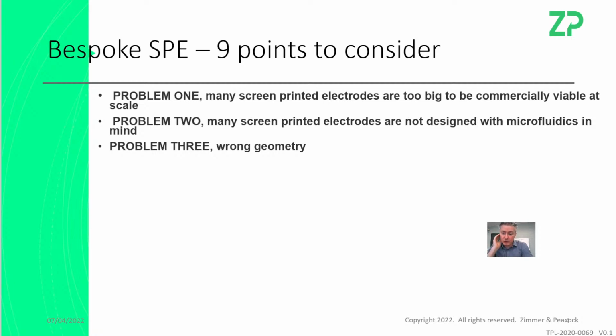So that would be an example of a wrong geometry. And sincerely, in our experience, interdigitated electrodes are not much better than much more macro, maybe rectangular electrodes or even circular electrodes. So, wrong geometry. The literature guides people. They take it sincerely, but actually in practice, it's not that much of an advantage.